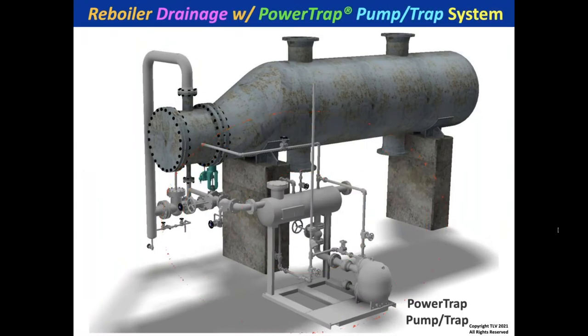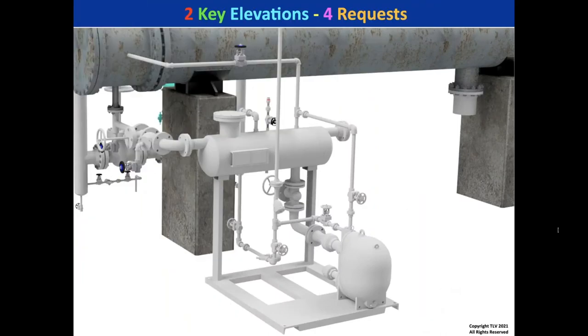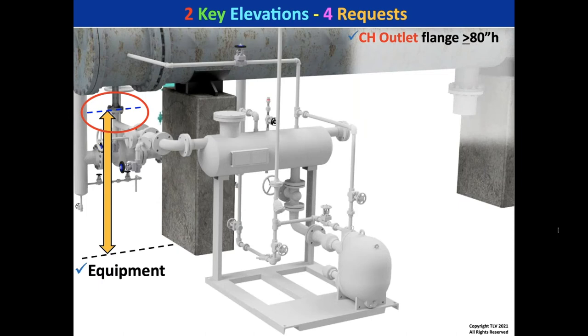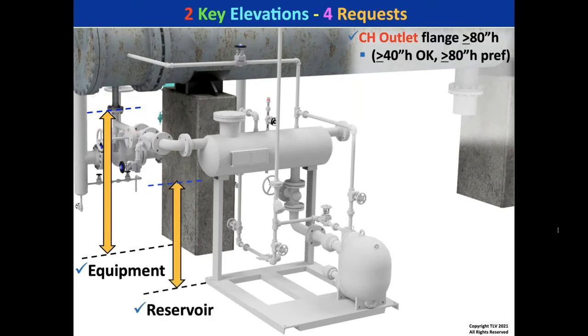Here's the kettle reboiler with a pump trap. The outlet flange on the channel head of the reboiler — shown by the blue line — should ideally be about 80 inches high on new designs. This makes it much easier to install a pump trap system. We can work as low as 40 inches, but that may mean purchasing an additional pump trap for the site for each application. So 80 inches is preferred.